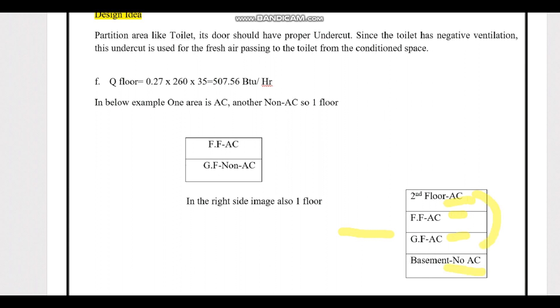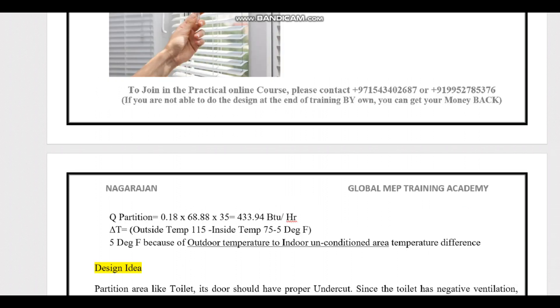For the non-AC area, we cannot expect the indoor temperature to be 75°F. The non-AC area has a different temperature, so we consider 5 degrees lower than the AC area. For example, where the AC area uses 40°F, the non-AC area uses 35°F.